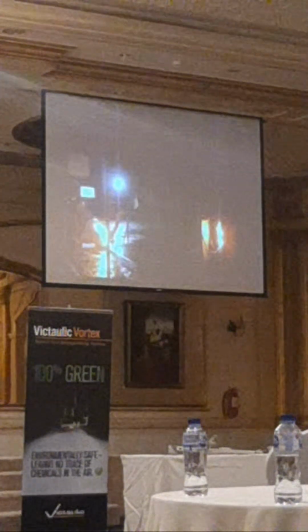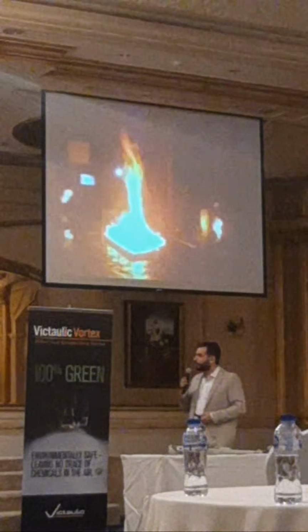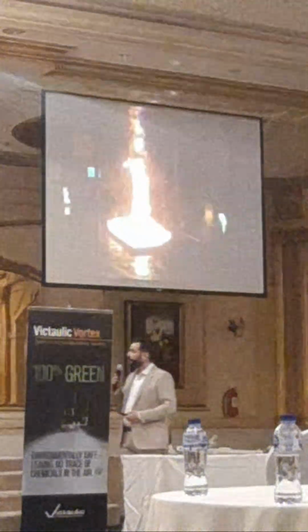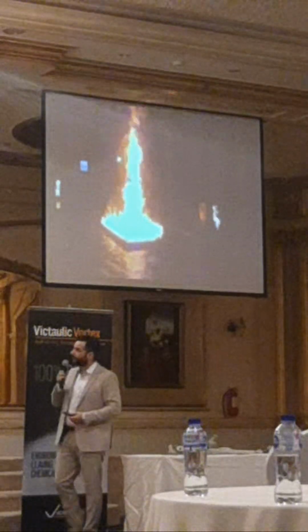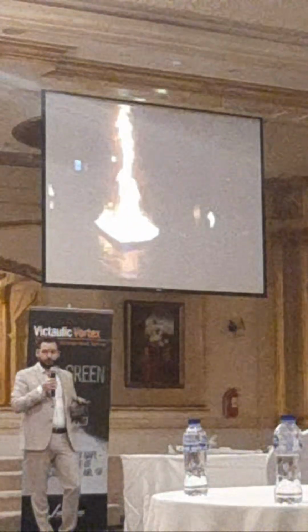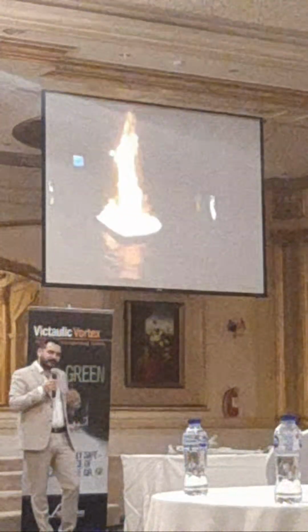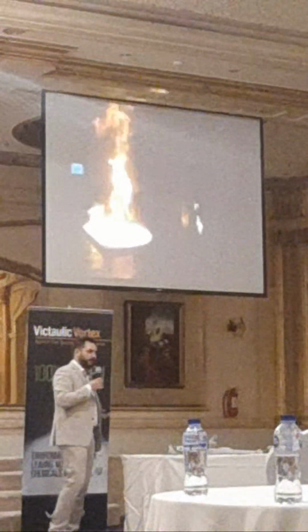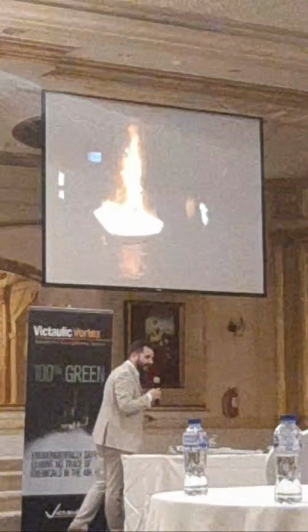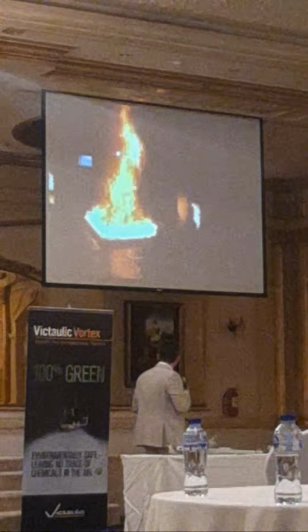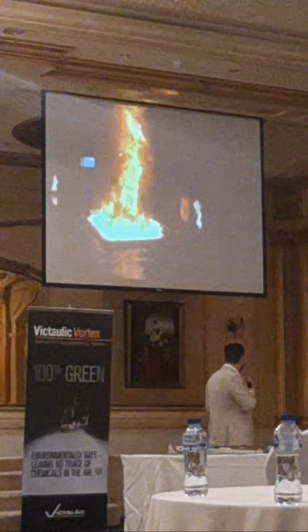One emitter, so 10 to 12 psi around. If you look closely at the top, you might see one of those emitters. There are 4 in total, one for every square meter at the bottom. It's a little different design than total flooding, but NFPA 770 also allows for total flooding. That's our local application.